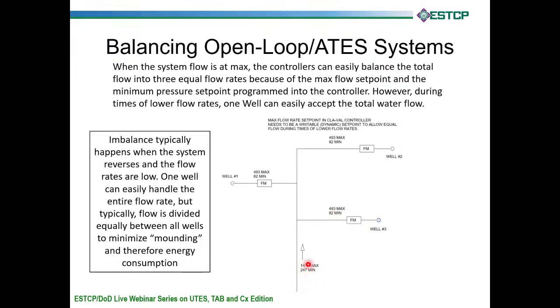So what we've seen happen is when the system reverses, when it changes direction from charging mode to discharging, from cooling to heating, however you want to talk about it, when this flow direction changes, then all these injection valves automatically start trying to get control. Well, one of them ends up getting control faster because it can take the whole 247. And so it just sits along there. It's sitting there and it's happy and it's getting all the flow rate, and these other guys are not getting anything.